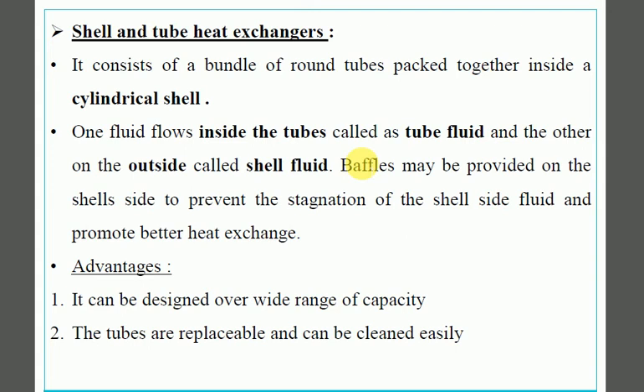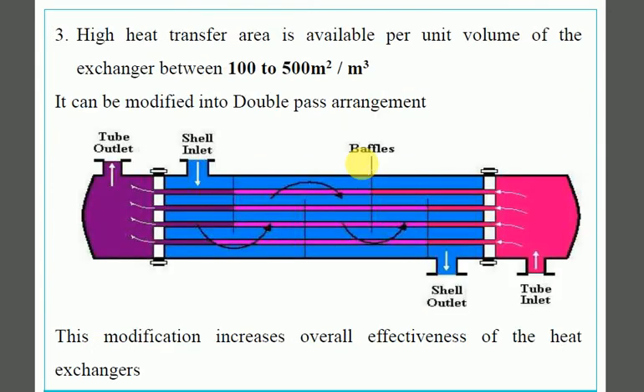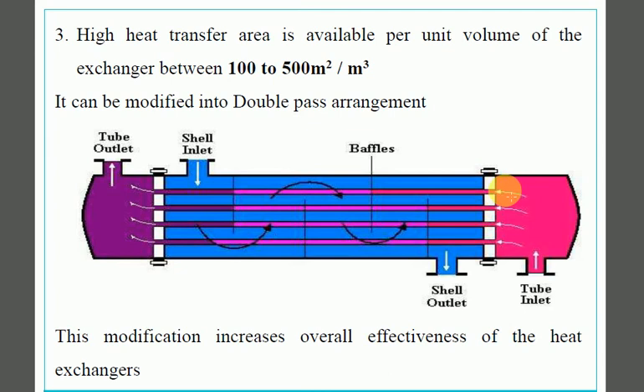The other type is the shell and tube heat exchanger. The arrangement is a modification of the double pipe arrangement. Cold fluid enters on one side and hot fluid is on the outside. Baffles create circular motion of liquid flow. Heat exchanging area increases — around 100 to 500 square metres per cubic metre per unit volume of the heat exchanger.